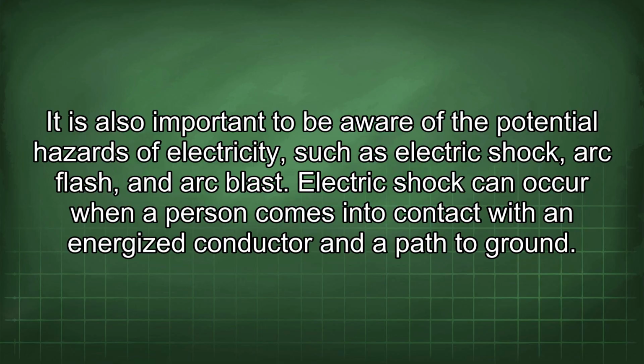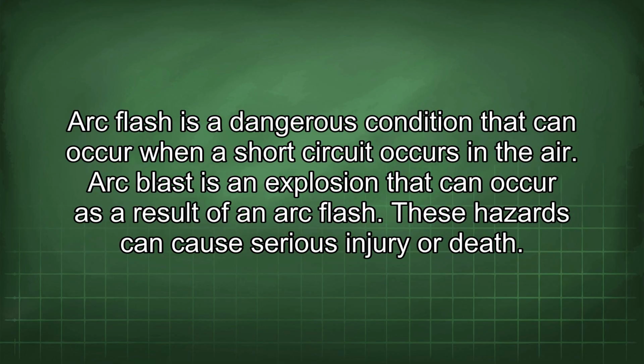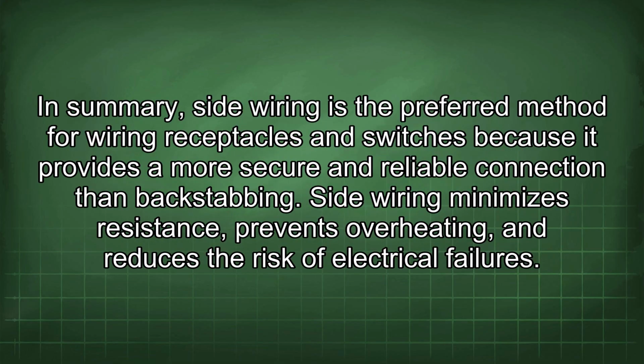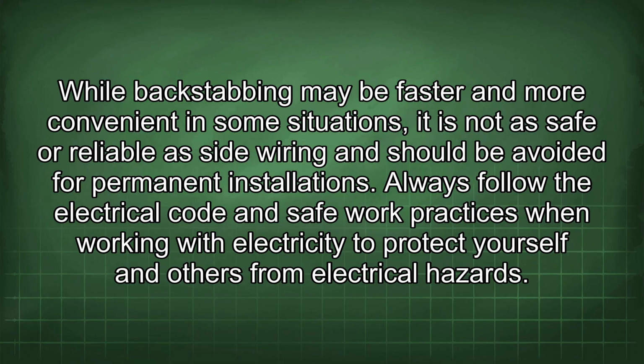Electric shock can occur when a person comes into contact with an energized conductor and a path to ground. Arc flash is a dangerous condition that can occur when a short circuit occurs in the air. Arc blast is an explosion that can occur as a result of an arc flash. These hazards can cause serious injury or death. In summary, side wiring is the preferred method for wiring receptacles and switches because it provides a more secure and reliable connection than backstabbing. Side wiring minimizes resistance, prevents overheating, and reduces the risk of electrical failures. While backstabbing may be faster and more convenient in some situations, it is not as safe or reliable as side wiring and should be avoided for permanent installations.